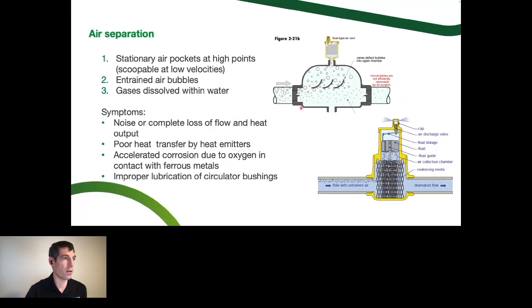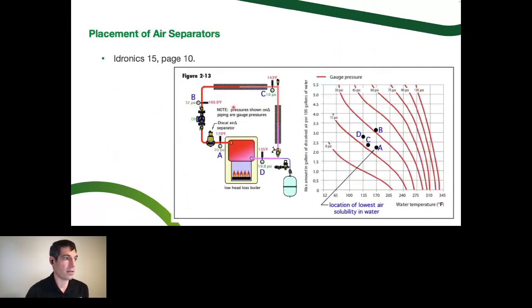The micro bubbles are going to go below these fins. They're carried by the velocity of the circulator. They're going to keep going and keep rusting other pieces of the system. So we don't want that. The last category is gases dissolved within the water, and that's actually related to expansion tank and circulator location in relation to the air separator. So you could have a great air separator just in the wrong spot, and you wouldn't get those gases dissolved in the water. So how we want to address that is to have the air separator on the hottest point of the system at the lowest pressure. So this is a chart that kind of shows where points A, B, C, and D line up. Point A is 170 degrees, so we've kind of cooked the water and we've cooked the air bubbles out of the water.